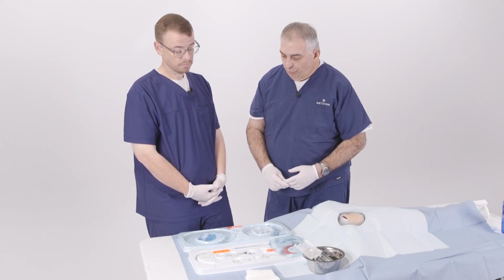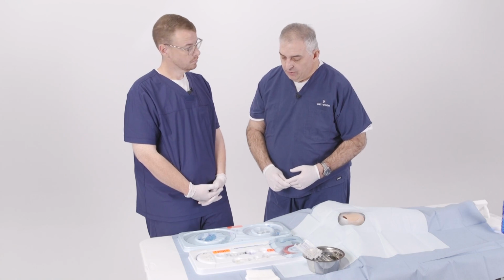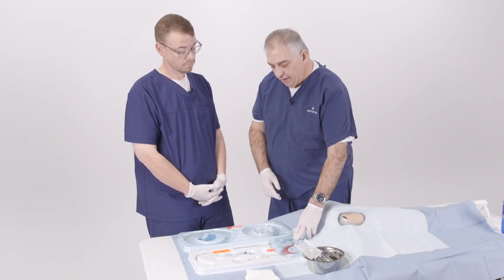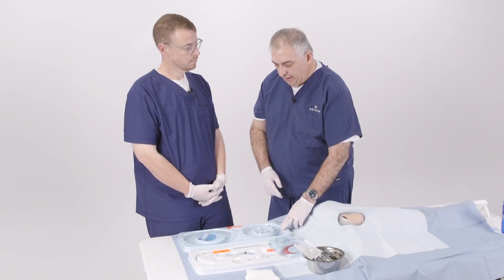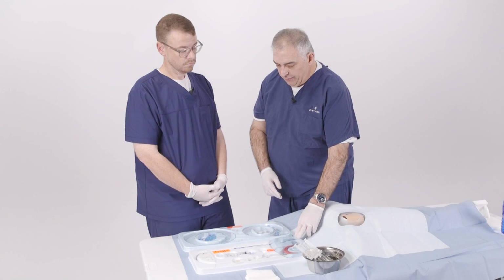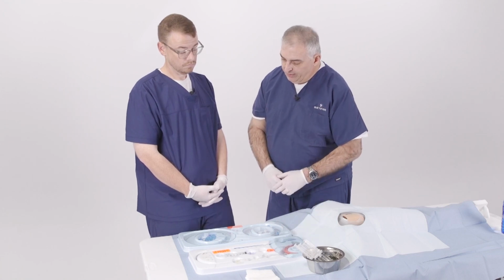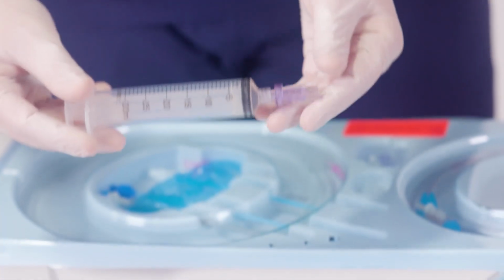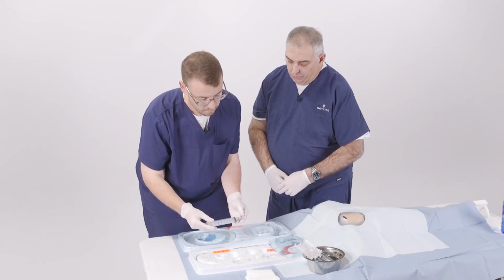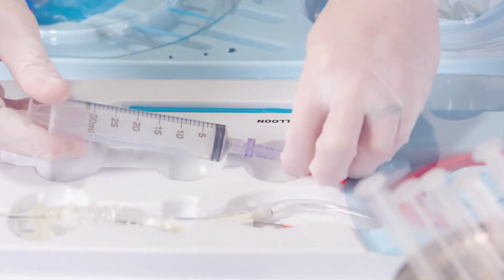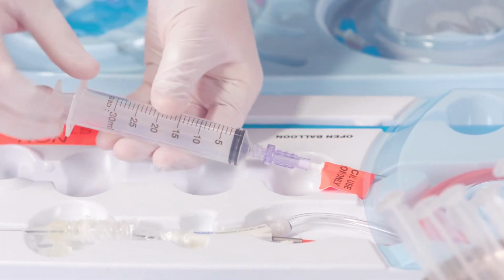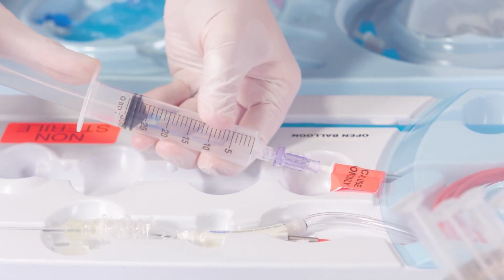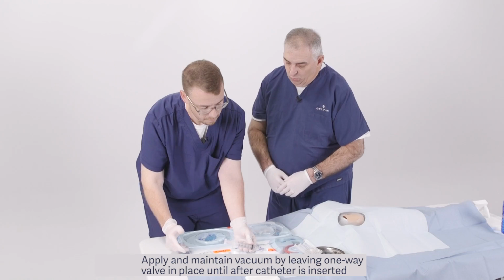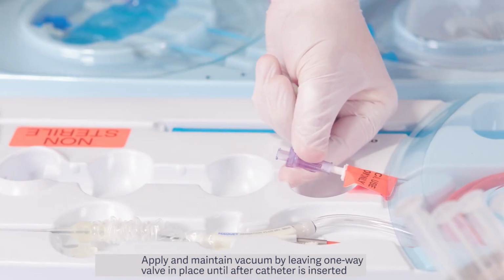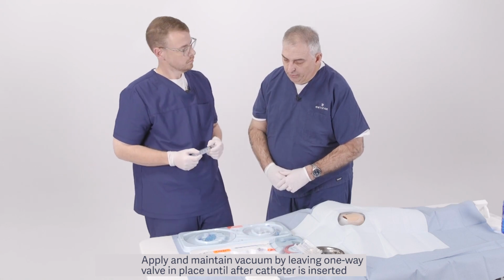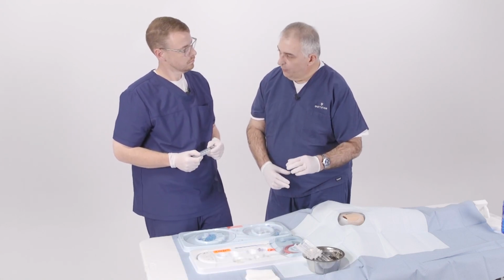When you open up the product box, you'll see that there are two trays included with the product. The first tray is the balloon tray, and the second tray is the insertion kit. So the first thing we're going to do is prepare the balloon by taking the 30 cc syringe with one-way valve attached. We're going to attach that to the extracorporeal tubing, and you're going to withdraw 30 cc's of air. When you do that, you're creating a negative pressure. Now, if you would take off the syringe, leaving the one-way valve in place, that will help to maintain that negative pressure, giving the balloon the lowest crossing profile to aid in insertion.